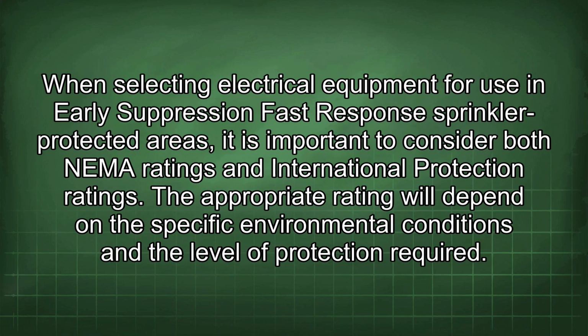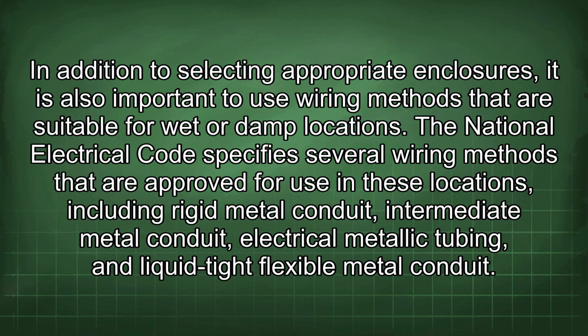When selecting electrical equipment for use in early suppression fast response sprinkler protected areas, it is important to consider both NEMA ratings and international protection ratings. The appropriate rating will depend on the specific environmental conditions and the level of protection required. In addition to selecting appropriate enclosures, it is also important to use wiring methods that are suitable for wet or damp locations.